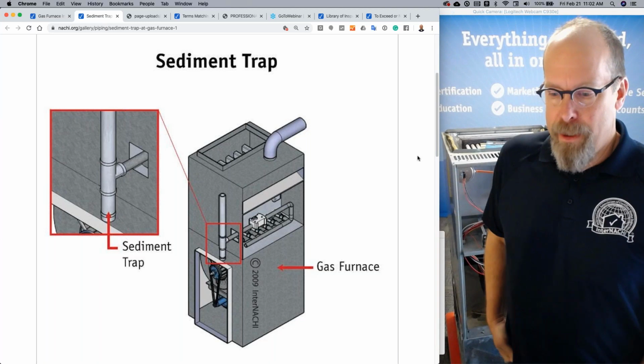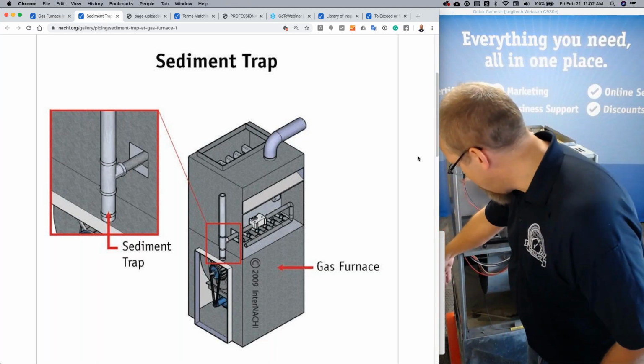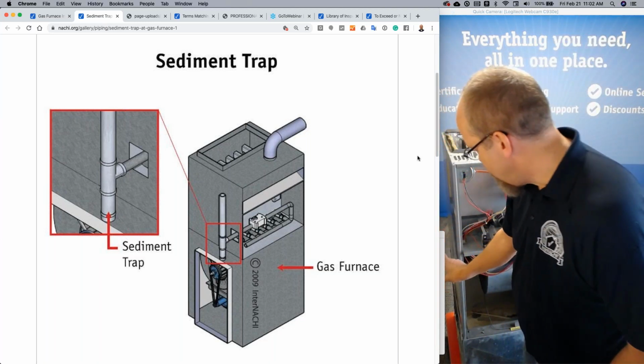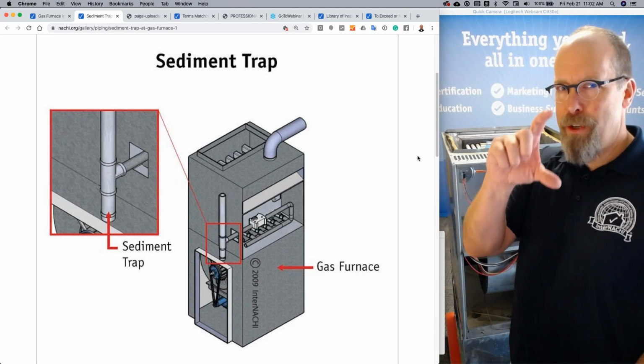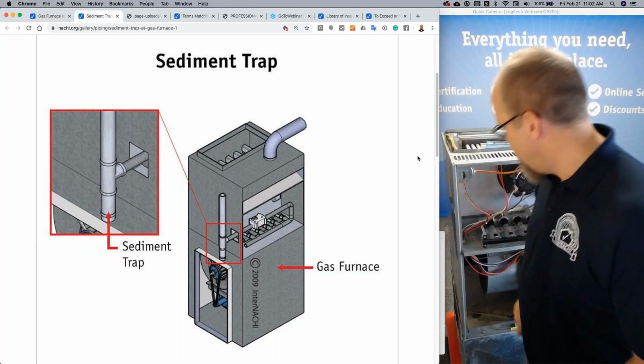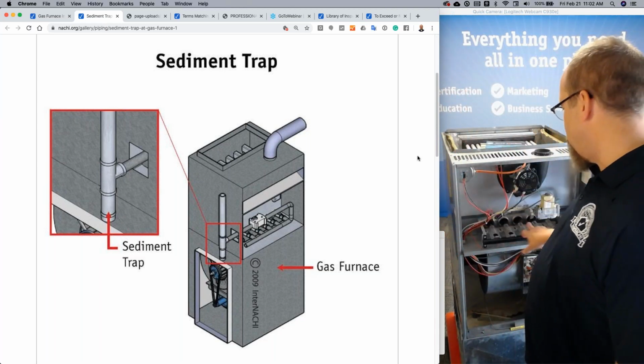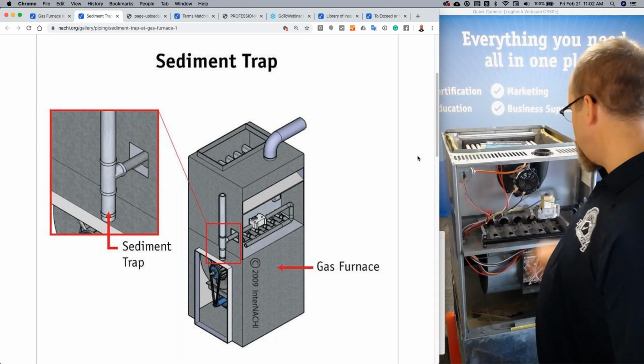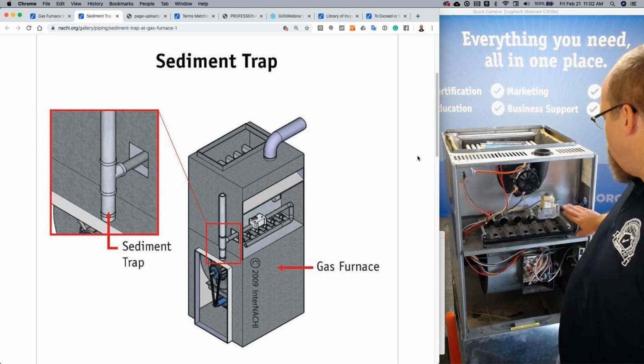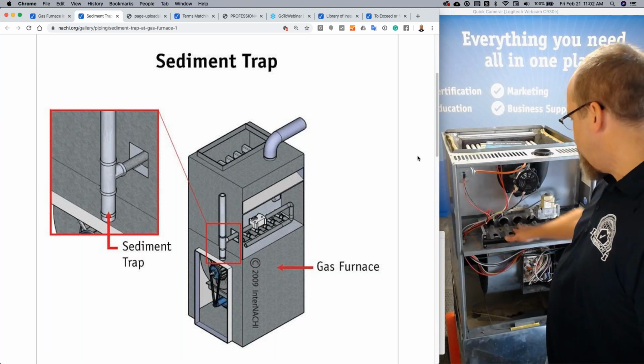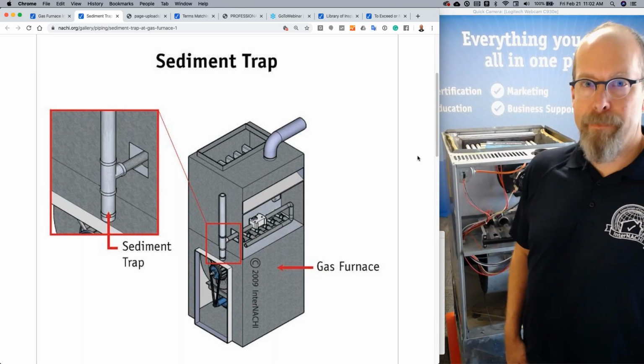It's this. So it's near the furnace. It's like a little leg that comes down. It's capped. It could be of any length. Usually it's only a few inches. And then the pipe, the hard pipe, no flexible pipe, comes from this T into the gas valve assembly here, which is then, this is the manifold and the in-shot burners. Yeah? Okay.